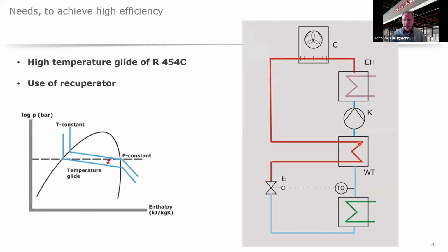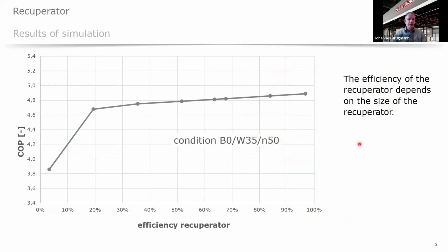But we had some problems with this recuperator, and I will show it here. In the lab, we measured roughly 0.8 COP points less than we simulated before. And the reason that we lost this efficiency was that the superheat, that is the heat exchange from the subcooling to the superheat, was not completely in the recuperator.